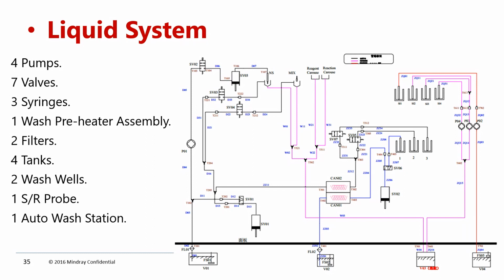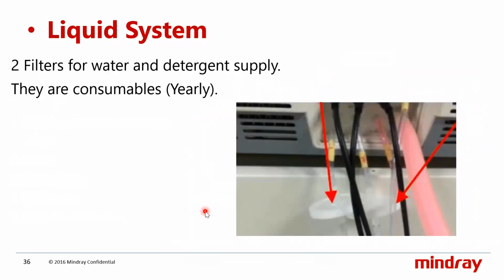Okay, so as I mentioned, the instrument has two filters. Filter 1 is connected to the deionized water input line, and filter 2 is connected to the detergent line. Okay, these two are consumables. You need to replace them yearly. It is a part of the PM kit. You can order through the PM kit.